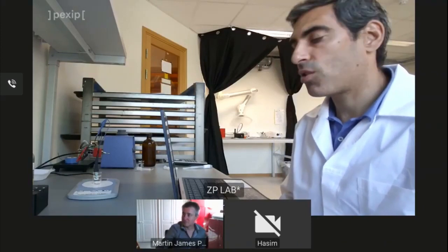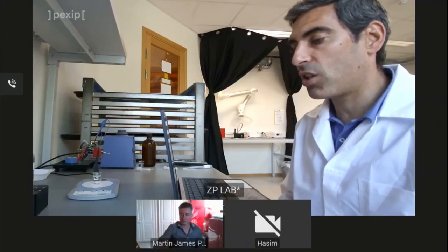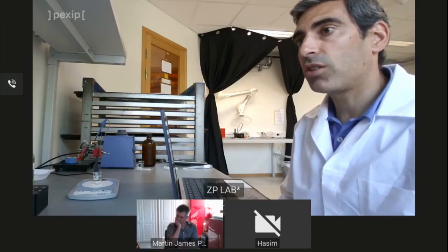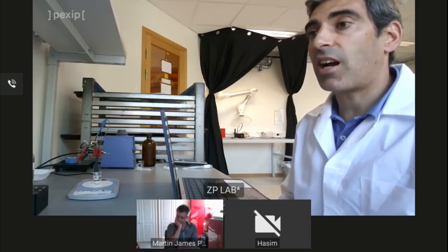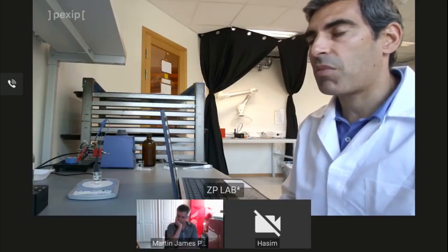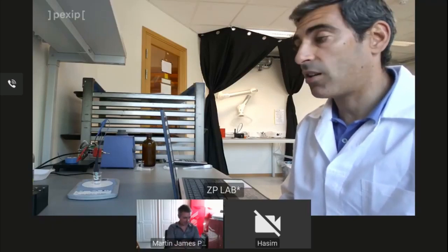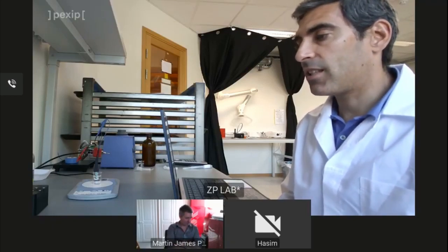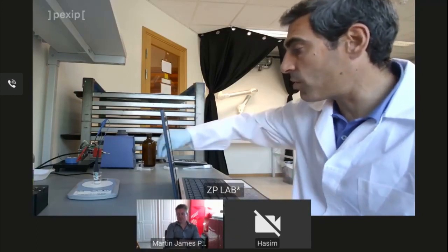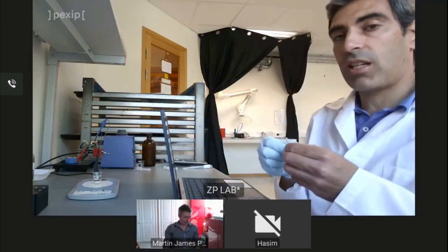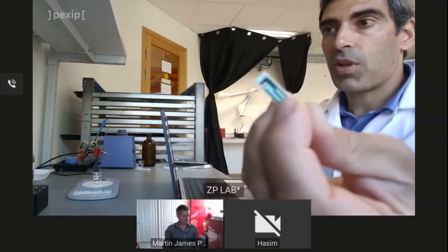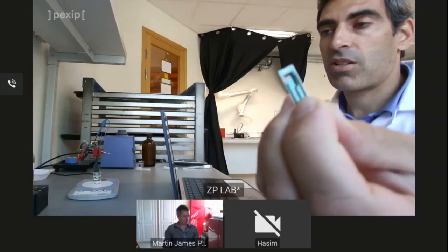Perfect. Good. All right. So what I'm going to demonstrate here now is actually a potentiometric measurement. So we are actually recording the potential. These are ion sensitive electrodes, so they have a membrane that's sensitive to the ion of interest. And in this case, I'm doing the demonstration of a sodium sensor.